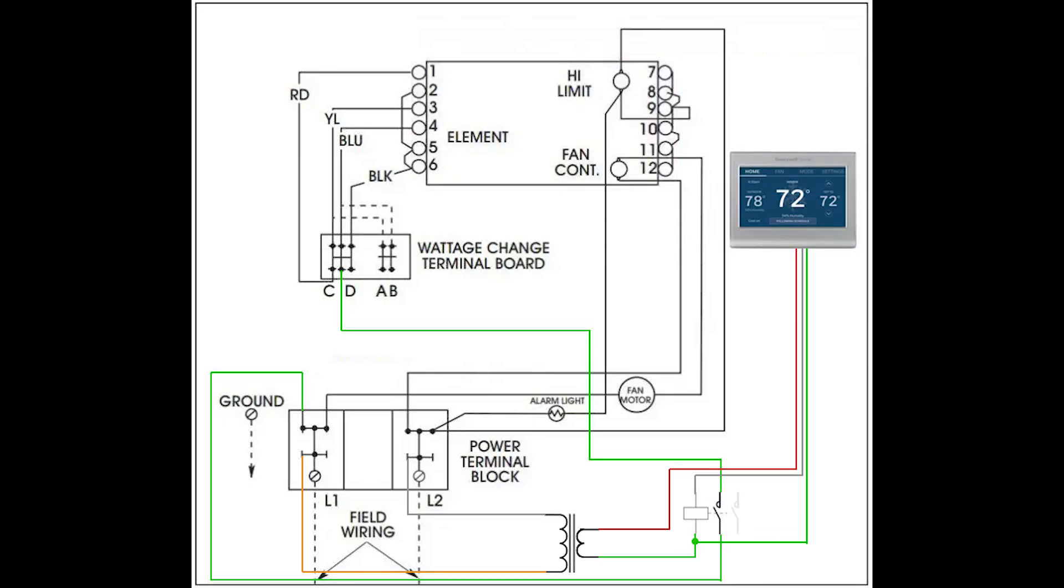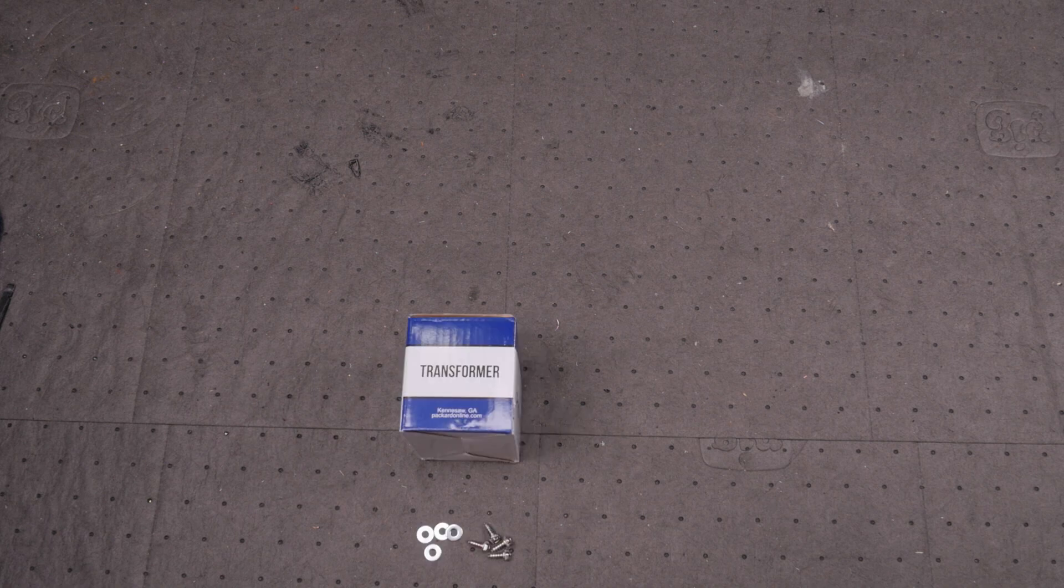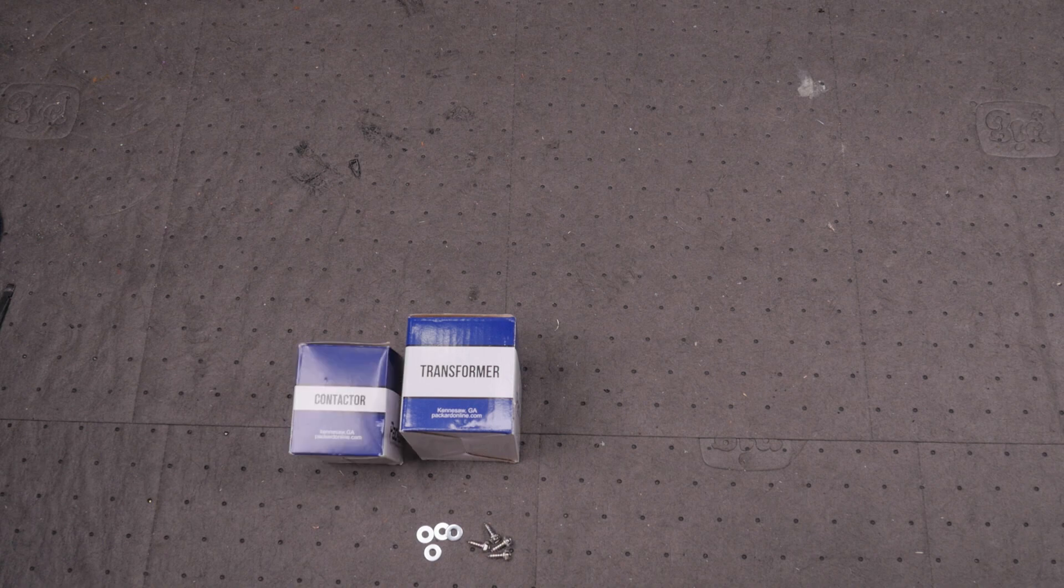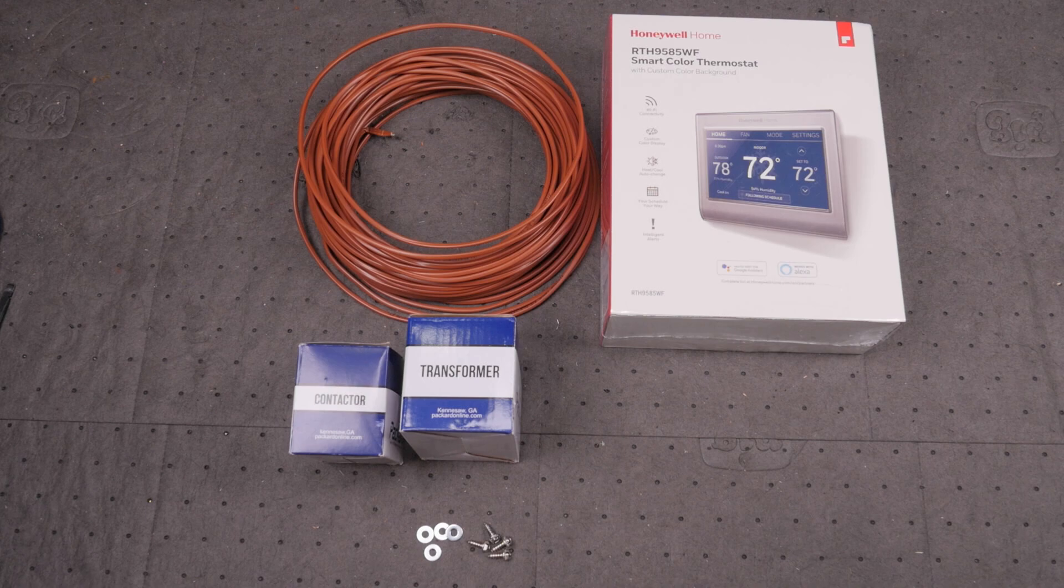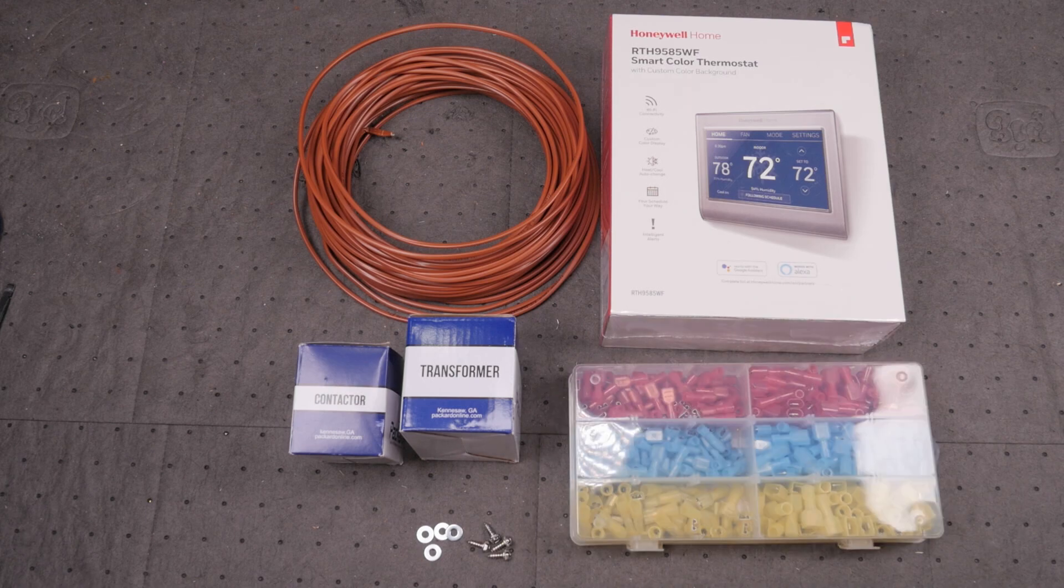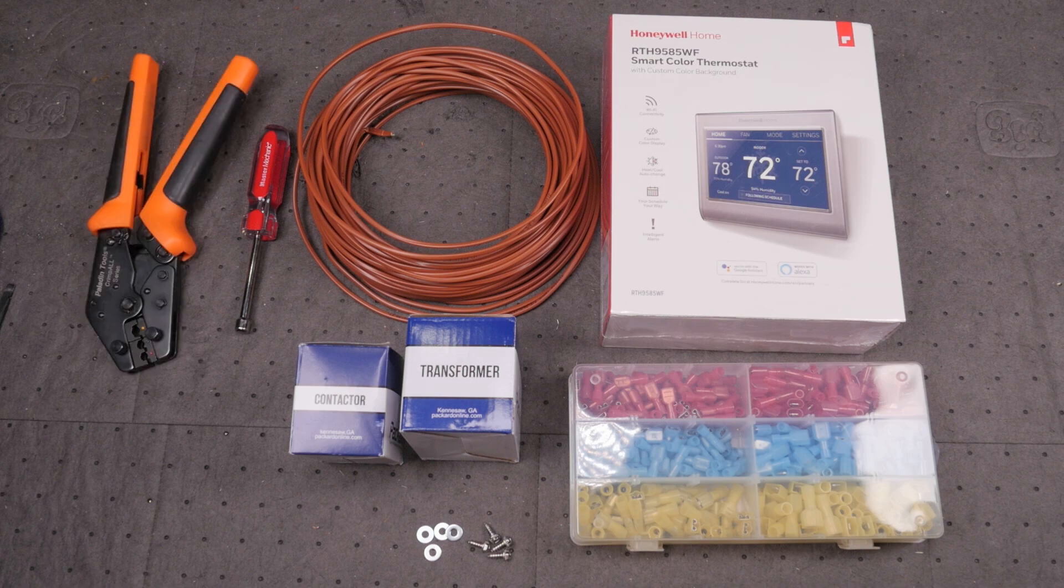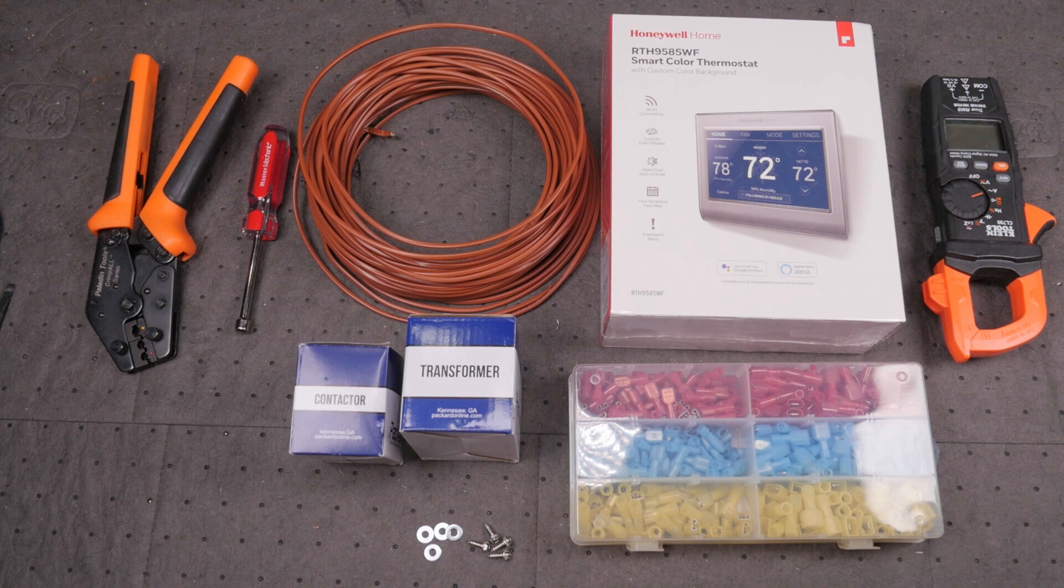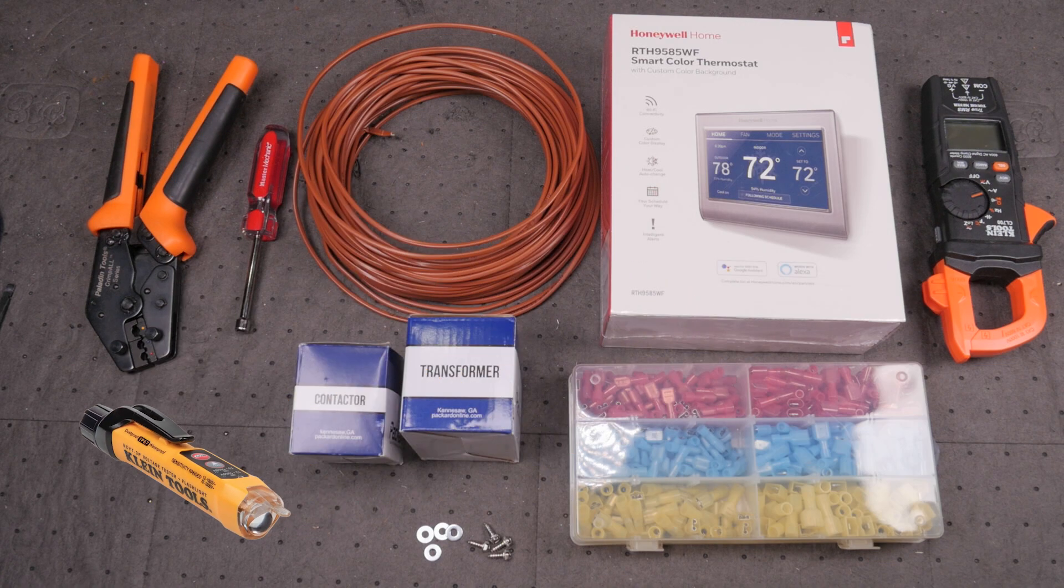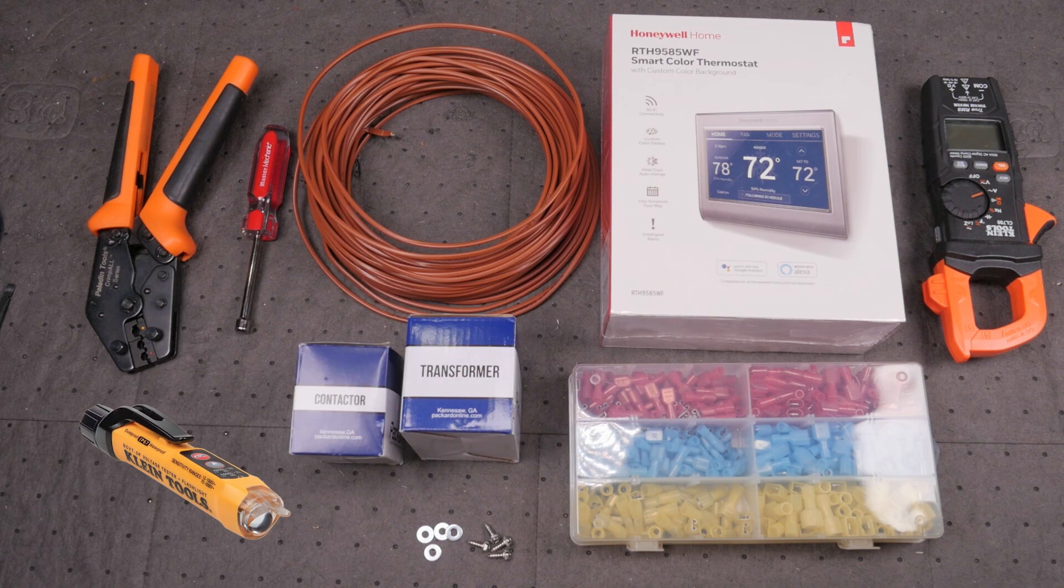Before we get to it, here's what you'll need for this project. Some sheet metal screws and washers. A 240 volt to 24 volt transformer. A contactor that can handle 20 amps. A Wi-Fi enabled thermostat. A length of at least 3 conductor thermostat cable. Appropriately sized crimp spade connectors. A nut driver or screwdriver. A crimp tool. Not completely necessary, but a multimeter and or ammeter. It's also a good idea to have a non-contact voltage tester for safety.